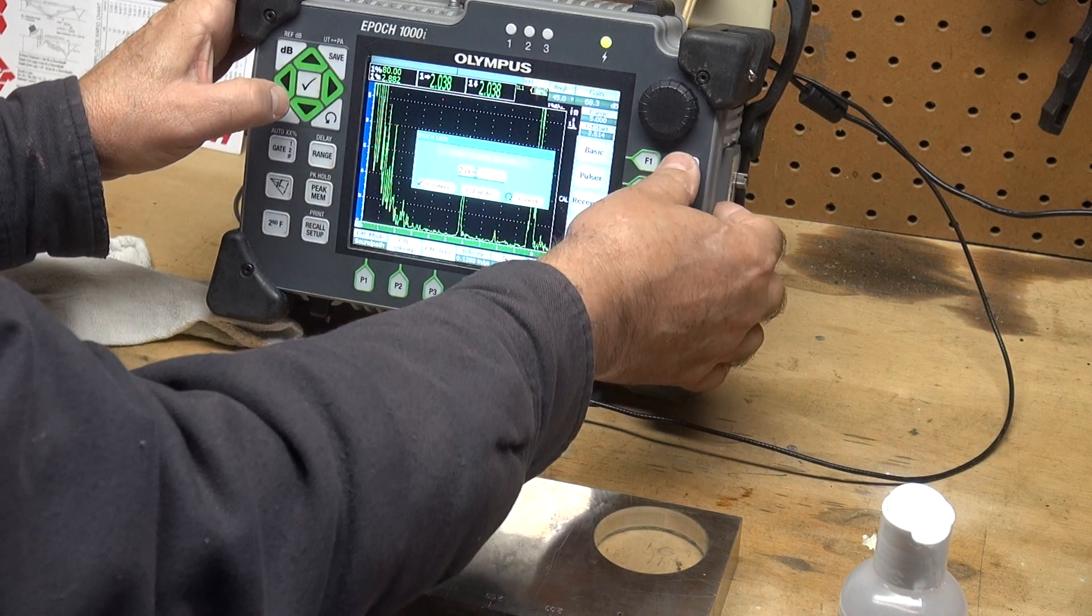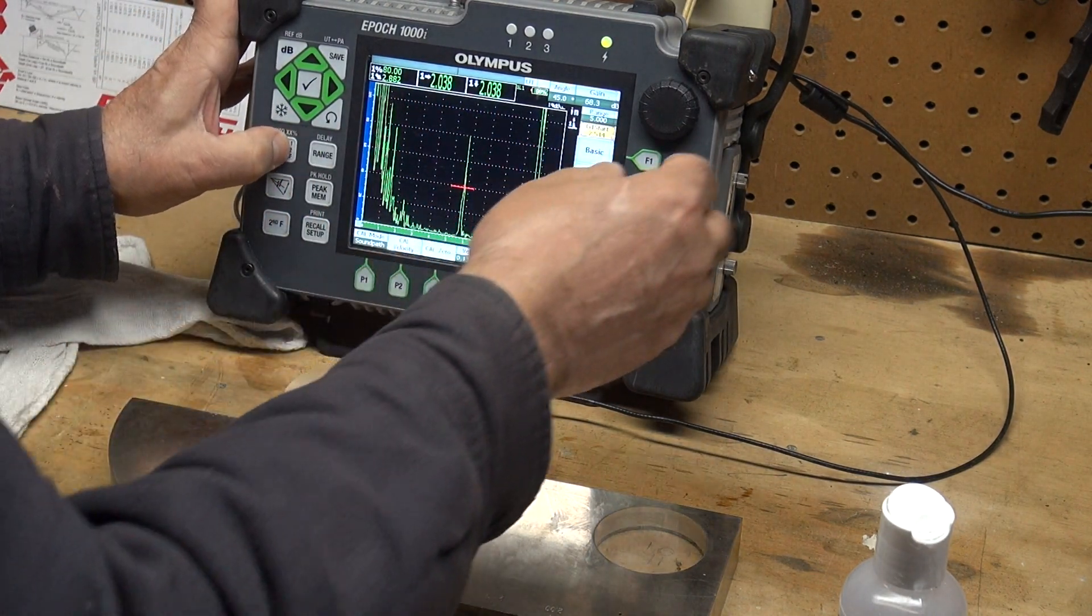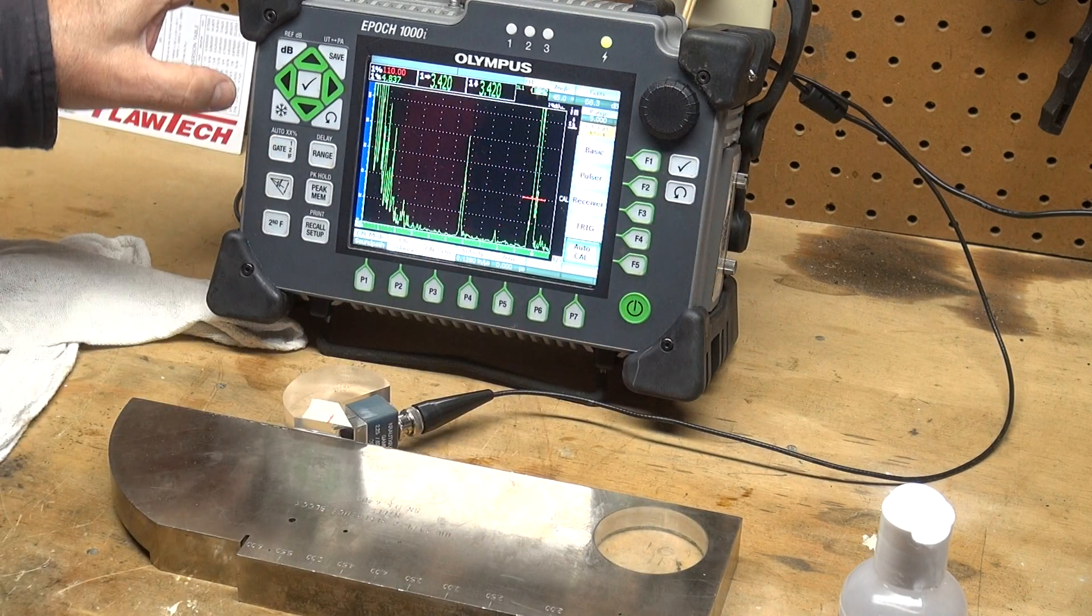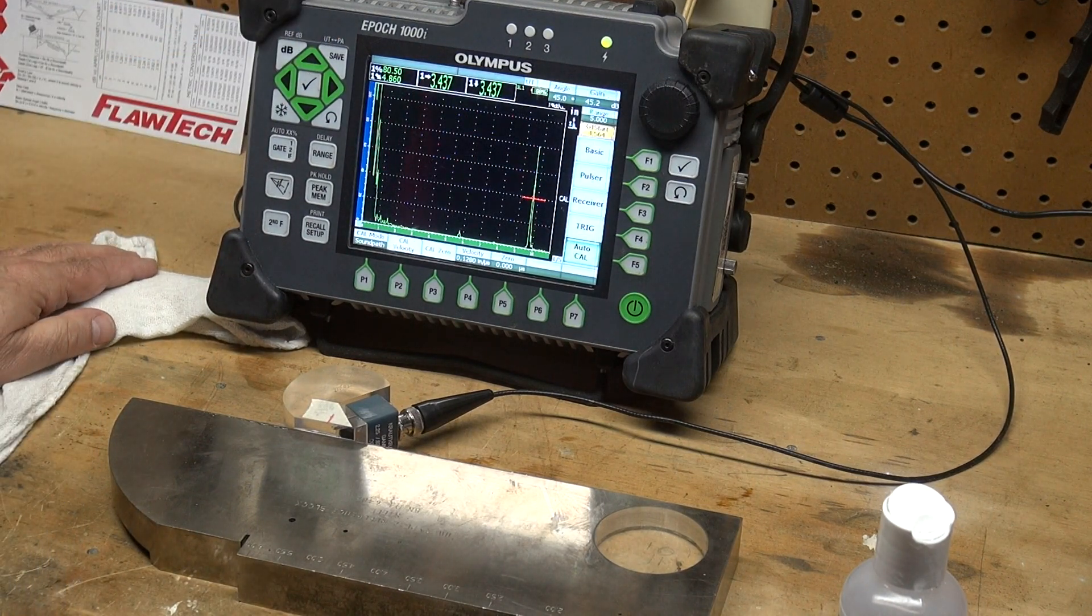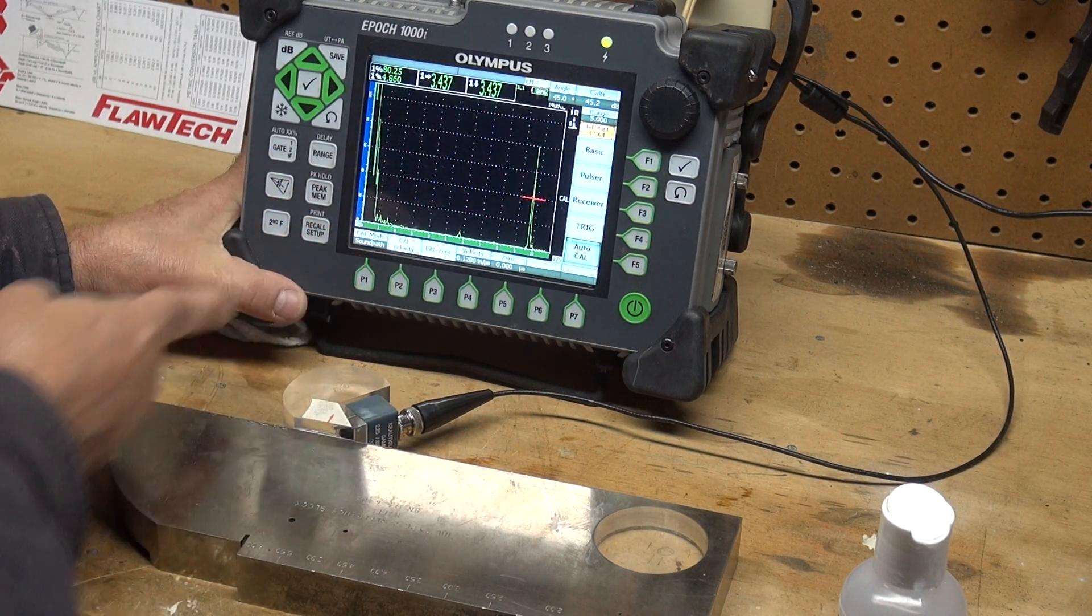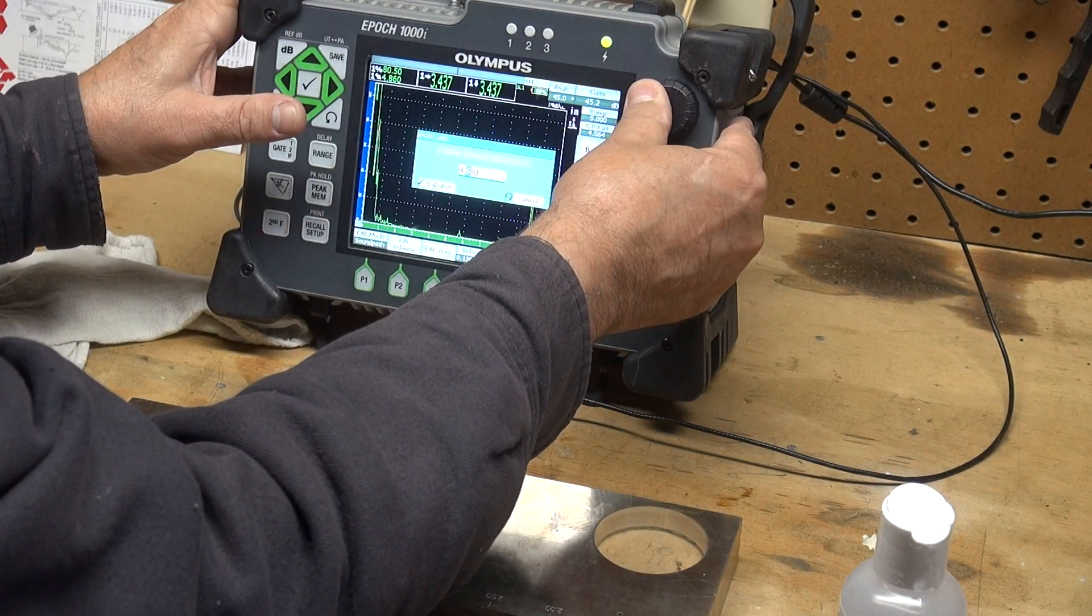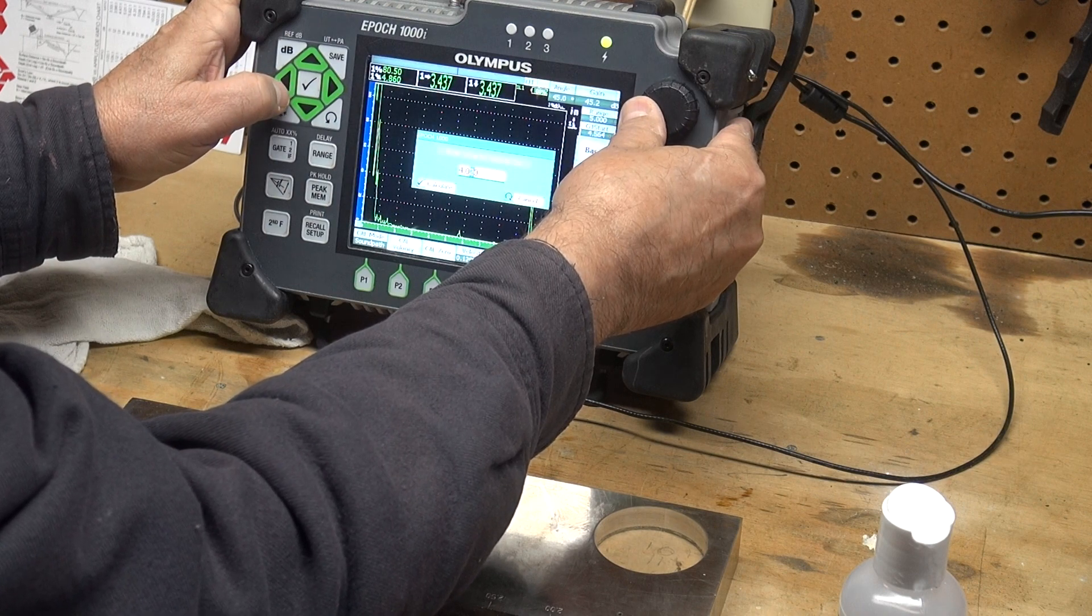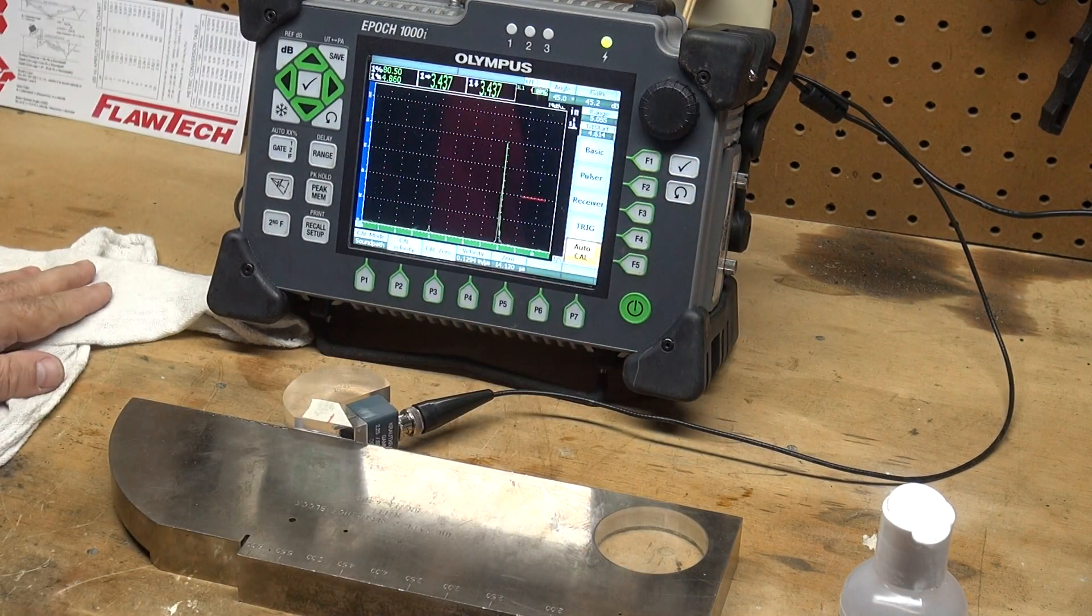Let me take my gate and move over to my 4 inch radius, which is this reflector right here. Again, I'll use auto 80 to bring it down to 80% full screen height. Then I'm going to press cal velocity. The machine is asking what is that sound path value and it's 4 inches. I'll adjust this to 4 inches and then the check mark will calculate and complete the calibration.